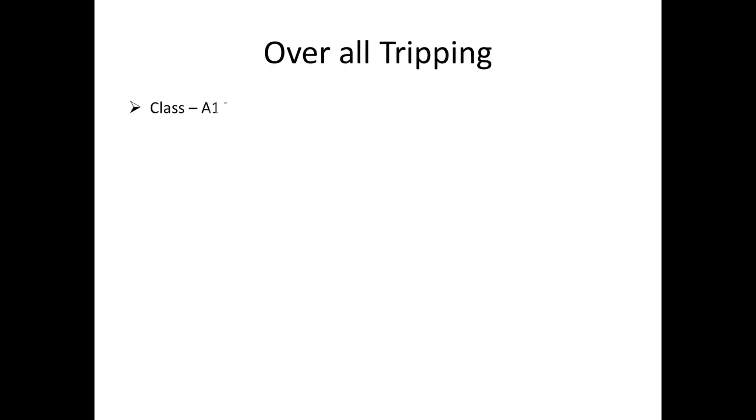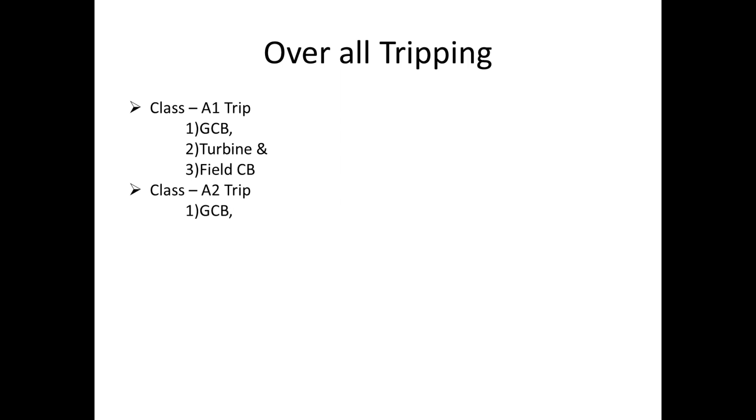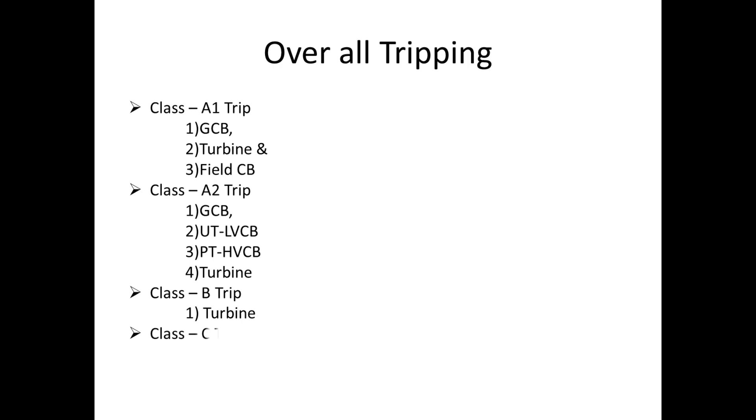Now we can see the overall tripping. Class A1 tripping: generator circuit breaker, turbine, field circuit breaker. Class A2 tripping: generator circuit breaker, utility LV circuit breaker, power transformer HV circuit breaker, turbine. Class B tripping: turbine. Class C tripping: power transformer HV circuit breaker.